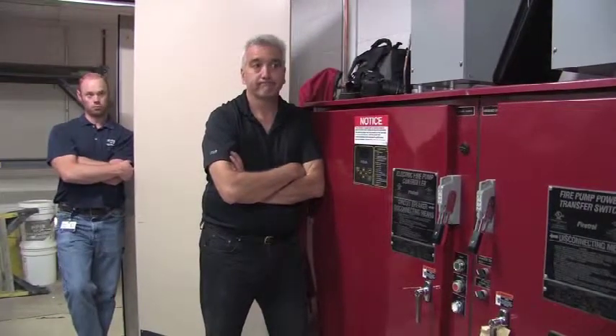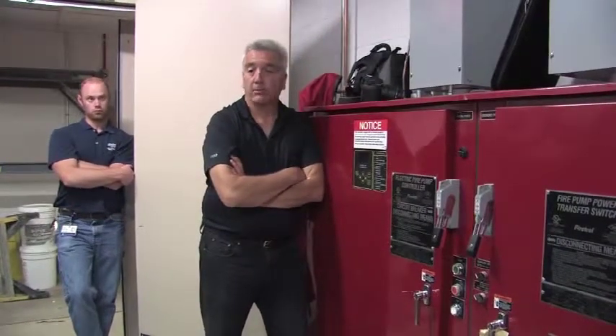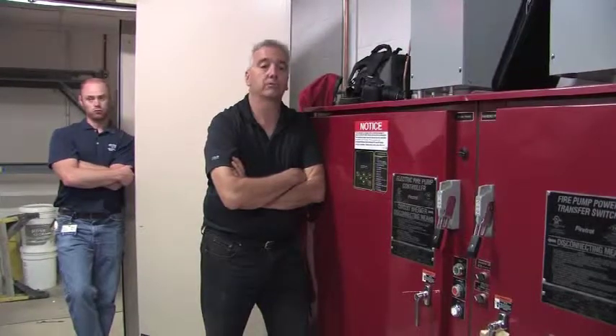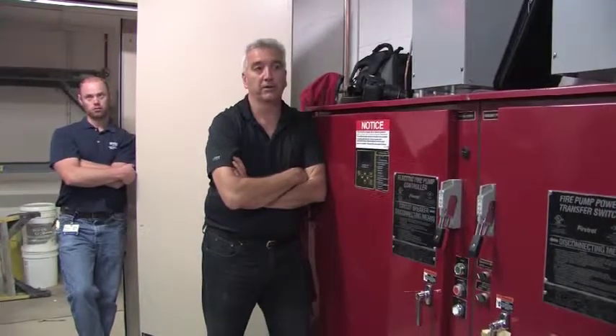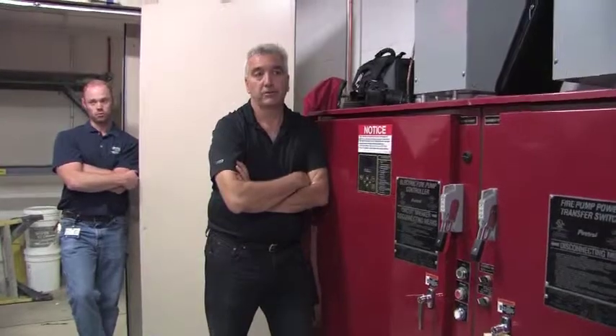We're familiar with all the other buildings, except for this one. Well, it's no different than your other buildings, except you've got to check it, make sure your casing relief valve works all the time, and just be smart about that part. That's what the casing relief valve is for, to introduce enough cold water into the pump so it doesn't get too hot on you.